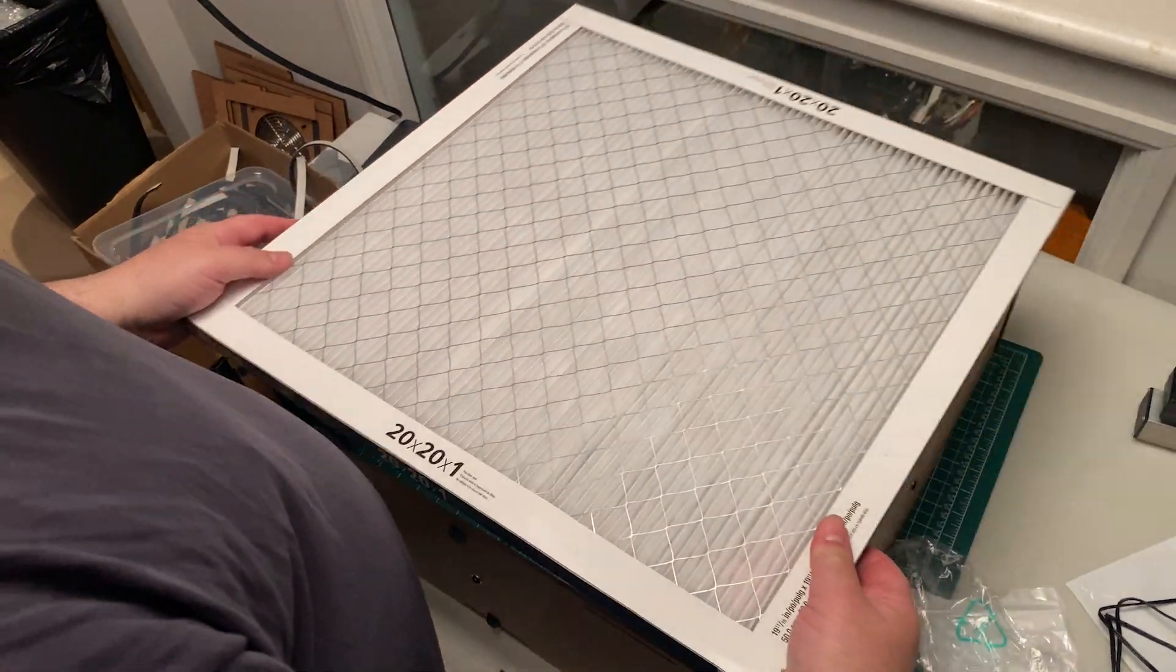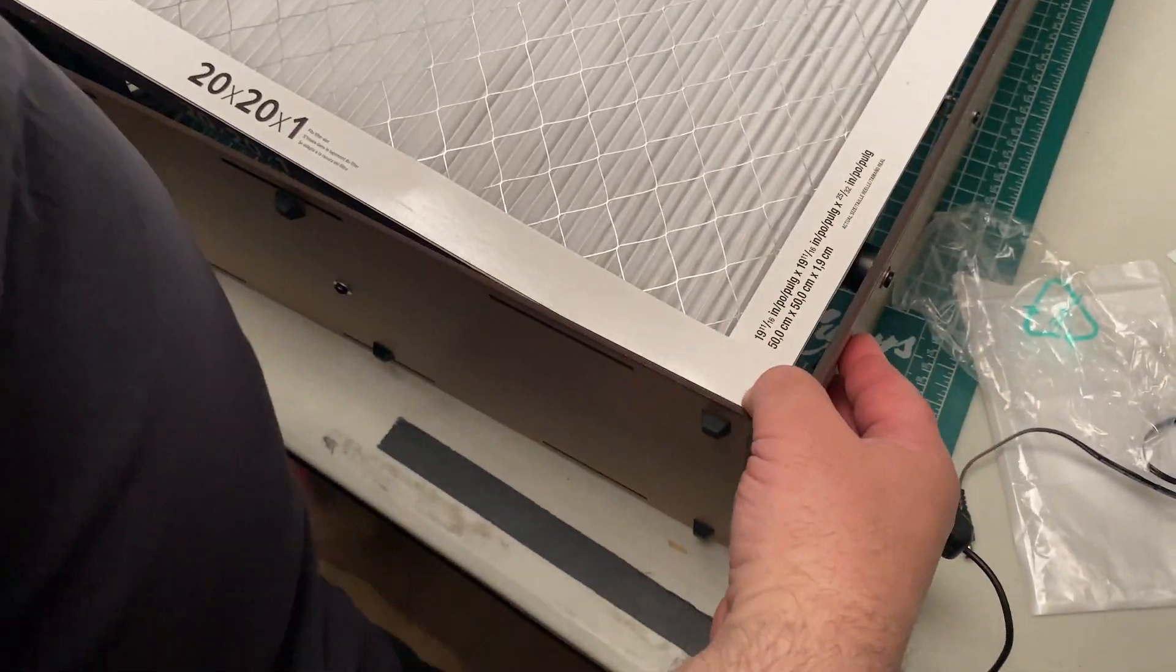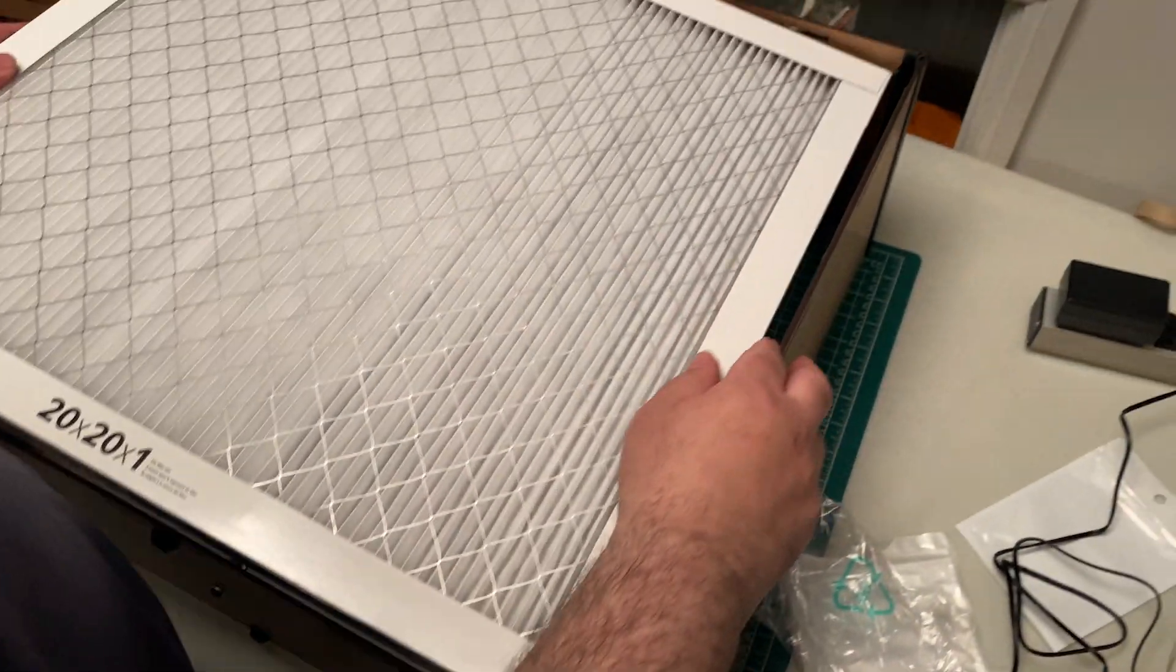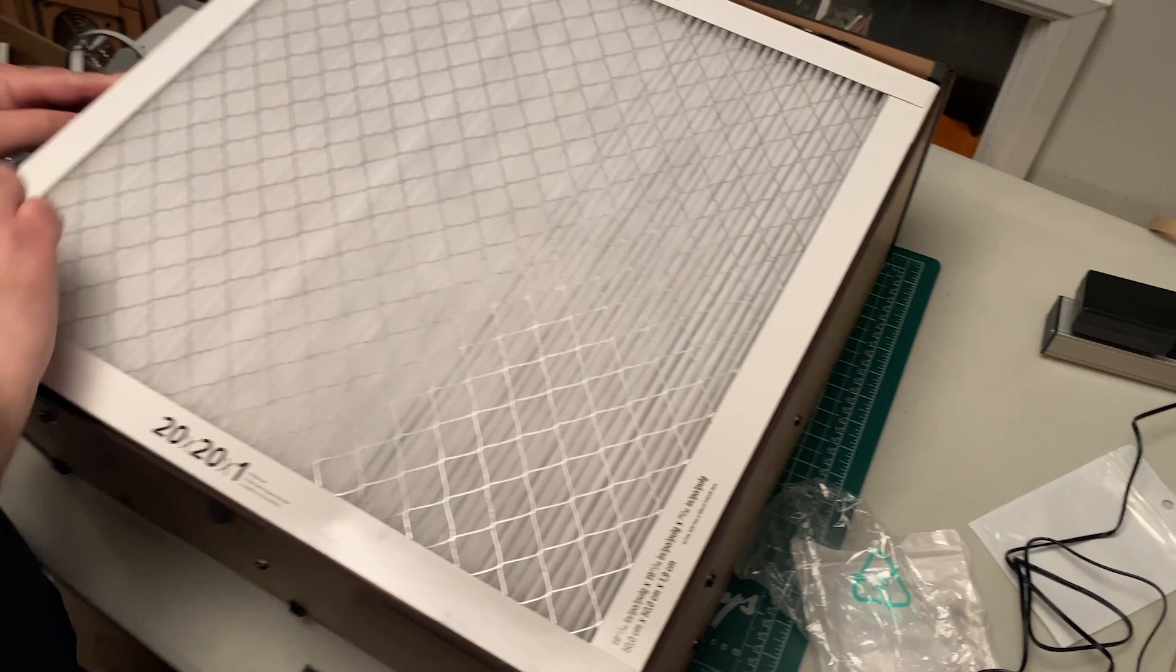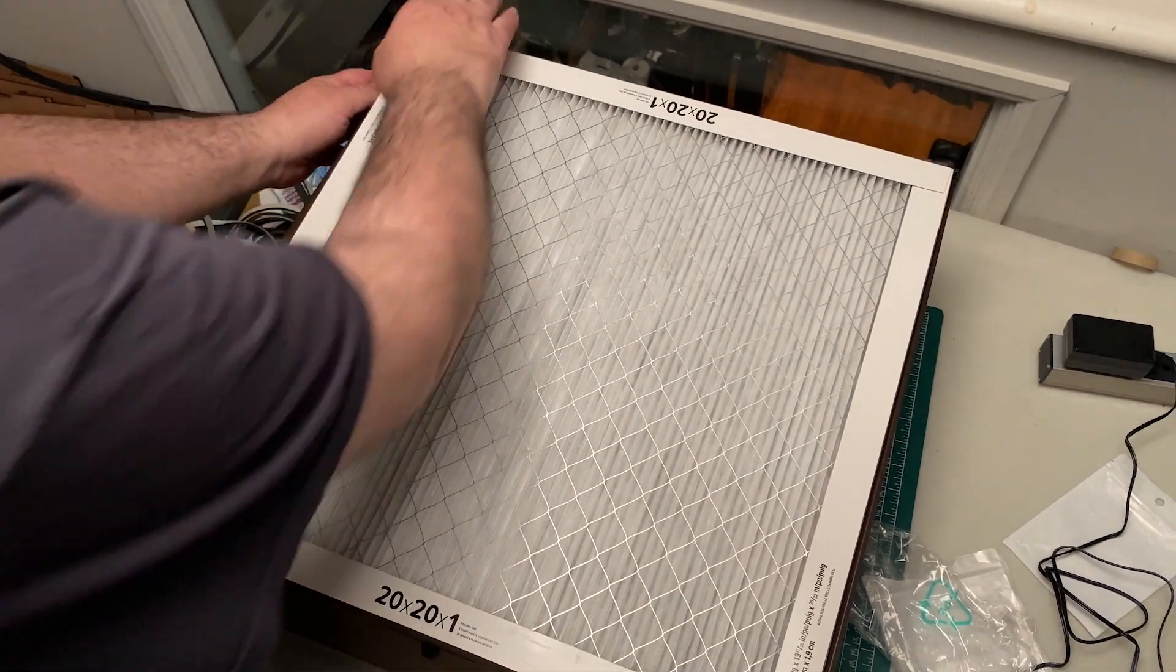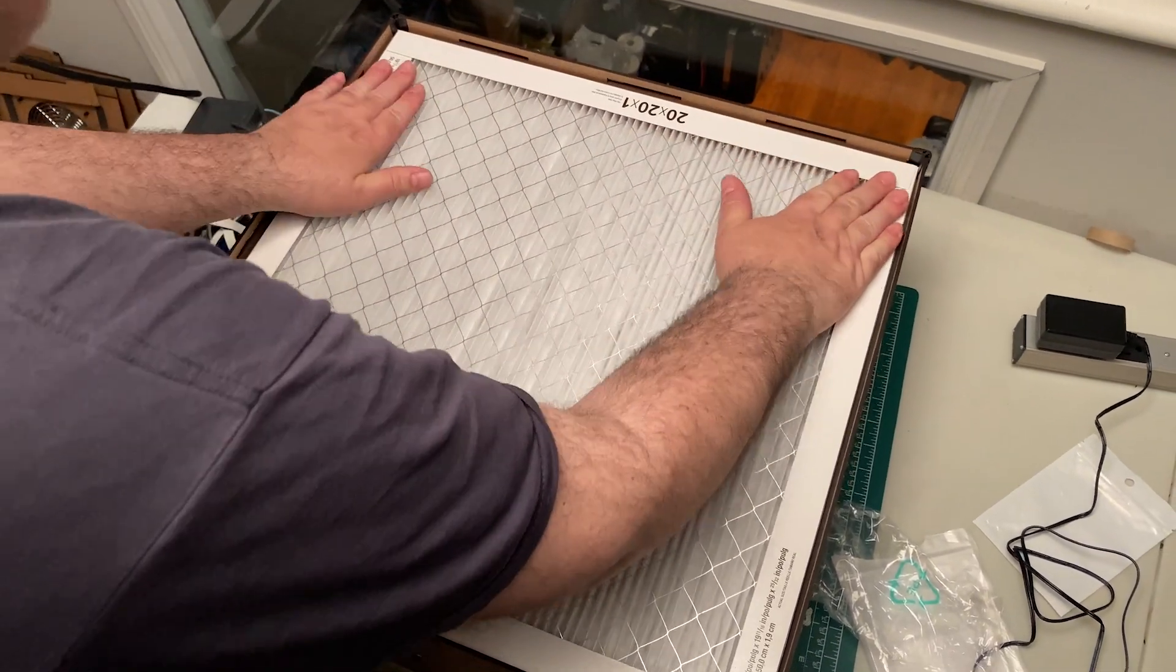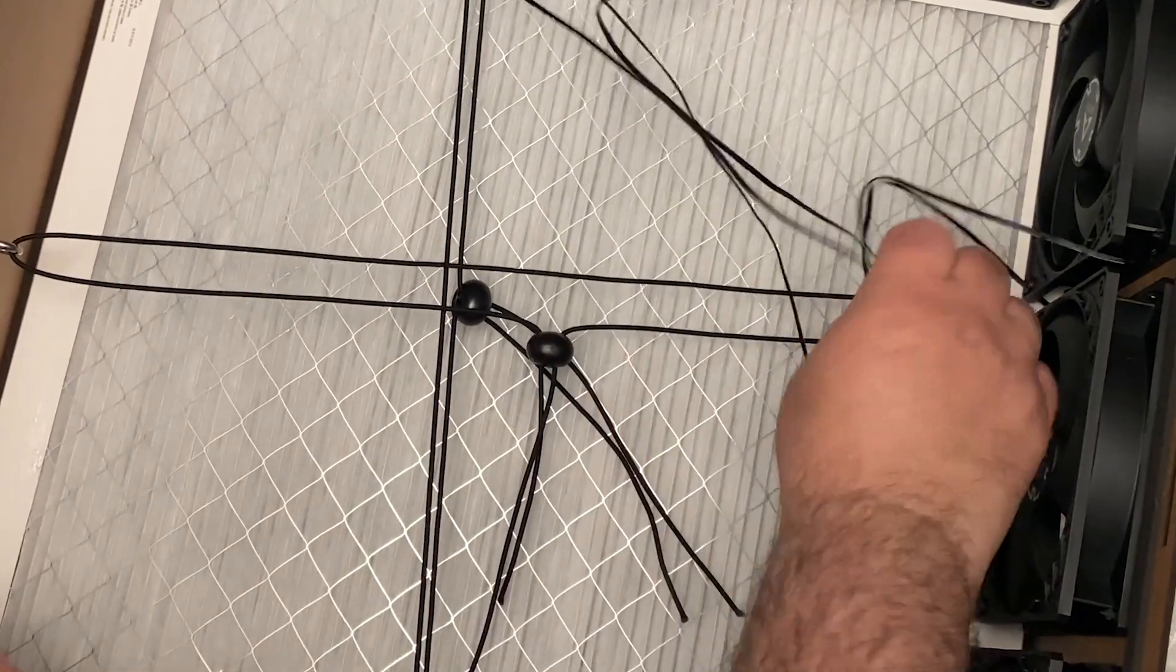The filters are designed for airflow to go in one direction. Just make sure that you see the 20x20x1 label is facing outwards. It's also a good idea to have the pleats of the filter going vertically, as they may sag over time.